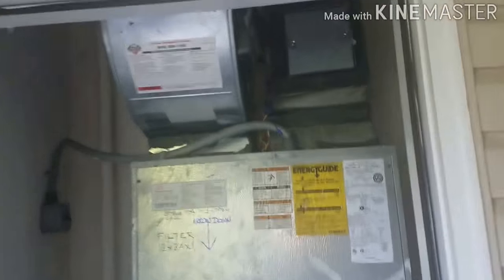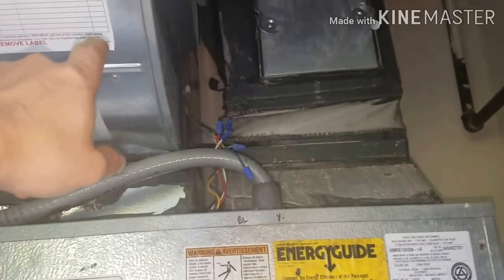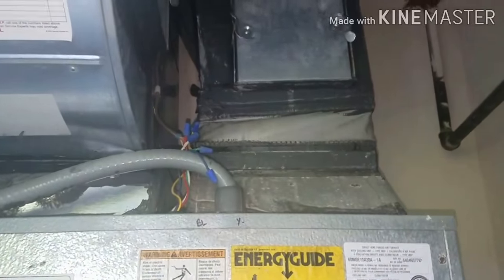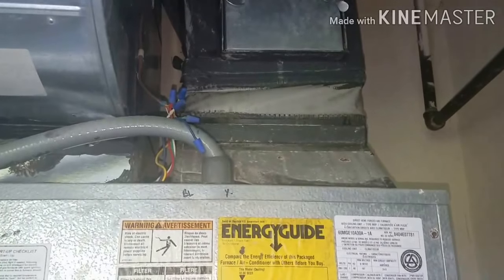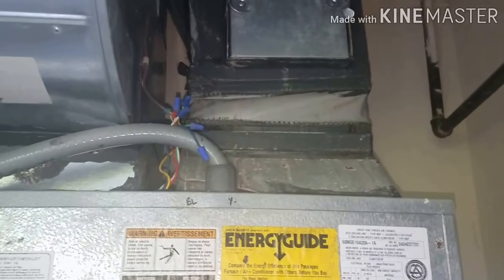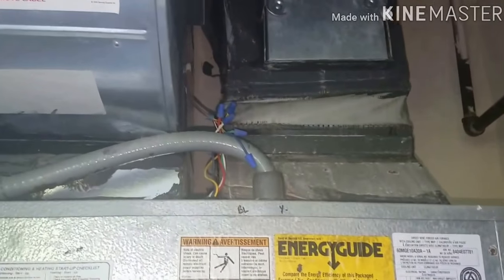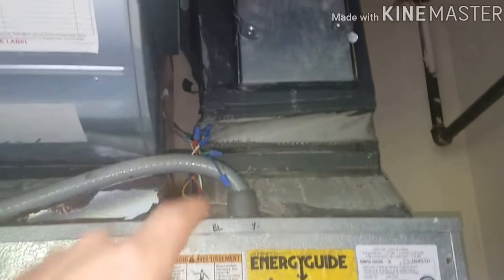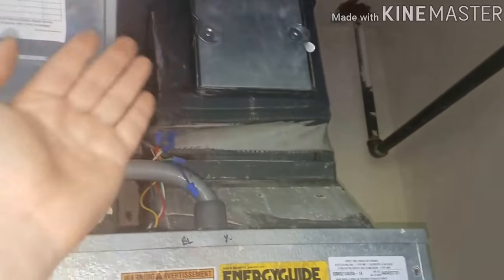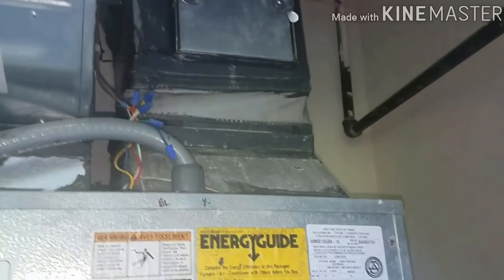That way fire doesn't spread throughout the building. Each return and supply in the ceiling has them — 2 inside there, and then the return has one in each bedroom. Everything has one. But these are very common to break, and then people call and say, well, my air conditioner's not working, my heat's not working, and I'm not feeling anything — and it's actually the supply or return damper that broke. They can be a pain to get up in there and hold that shut while you replace that fusible link.